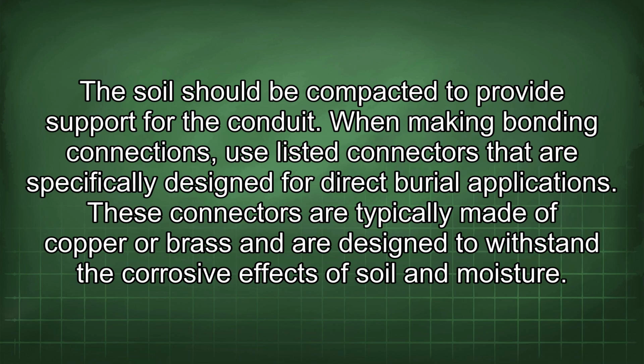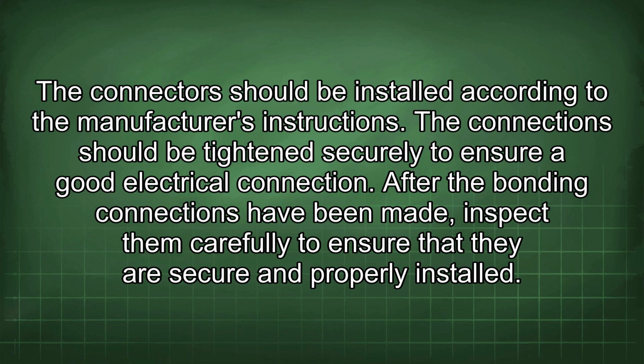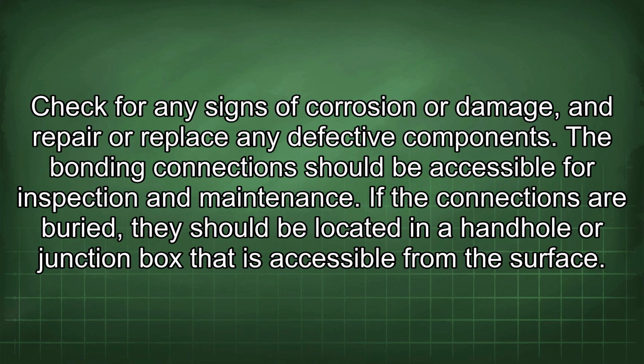When making bonding connections, use listed connectors that are specifically designed for direct burial applications. These connectors are typically made of copper or brass and are designed to withstand the corrosive effects of soil and moisture. The connectors should be installed according to the manufacturer's instructions. The connections should be tightened securely to ensure a good electrical connection. After the bonding connections have been made, inspect them carefully to ensure that they are secure and properly installed. Check for any signs of corrosion or damage, and repair or replace any defective components. The bonding connections should be accessible for inspection and maintenance.